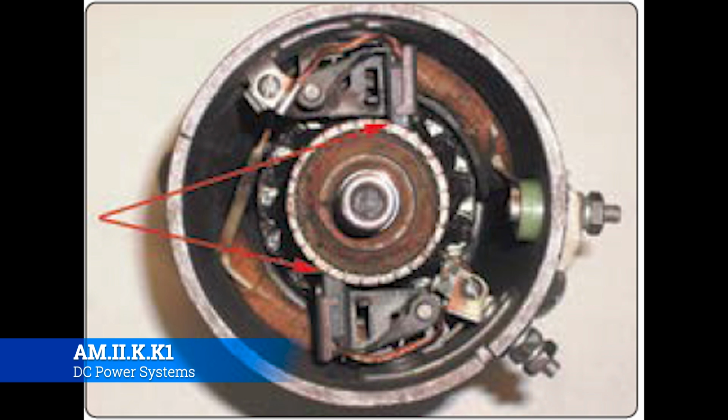I will tell you, a lot of that's really uncommon. These are pretty simple devices, and they're pretty reliable. Outside of a little bit of brush maintenance and blowing them out with air and stuff like that, it's just general maintenance that you would do on just about anything.